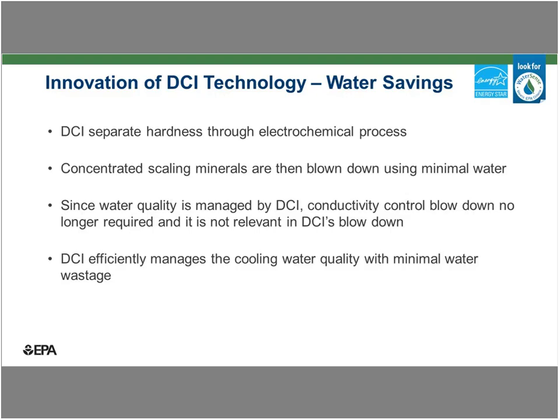In fact, it's irrelevant for us. The reason people use conductivity is the assumption that when the conductivity goes up, your scaling minerals go up in tandem. But because DCI is removing scaling minerals selectively, the other non-scaling minerals may contribute to the conductivity reading, but they are not going to cause scaling. So DCI efficiently manages the cooling water with minimal water wastage.